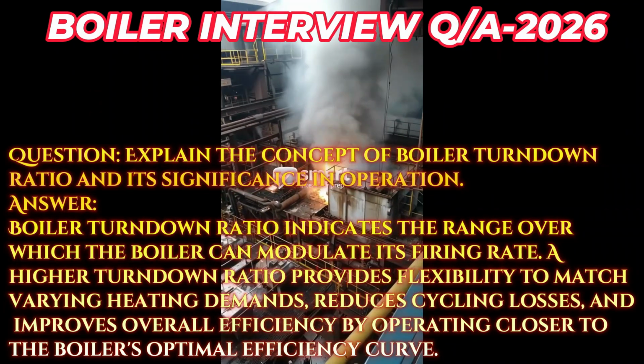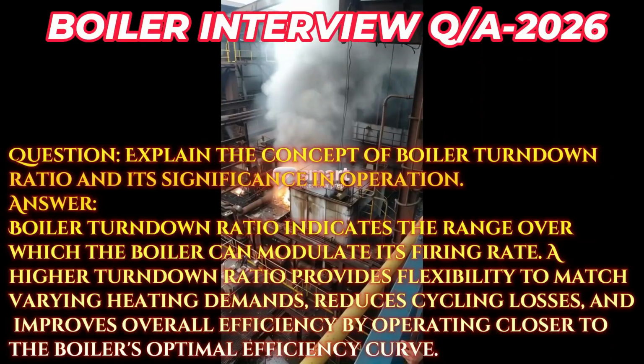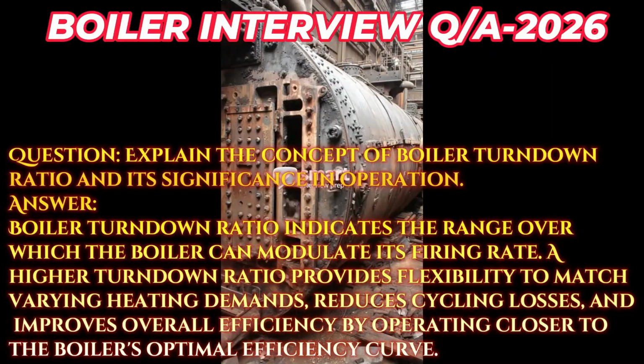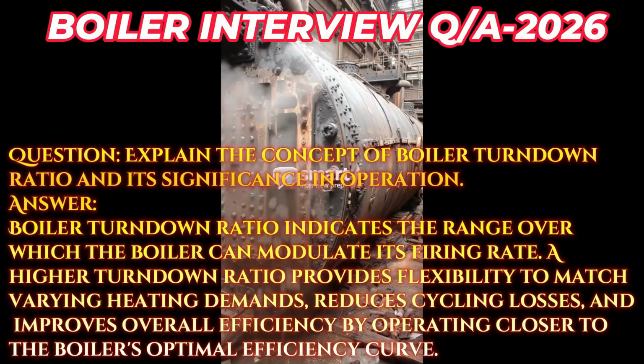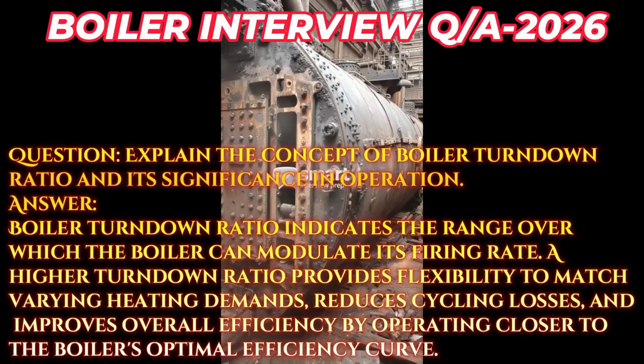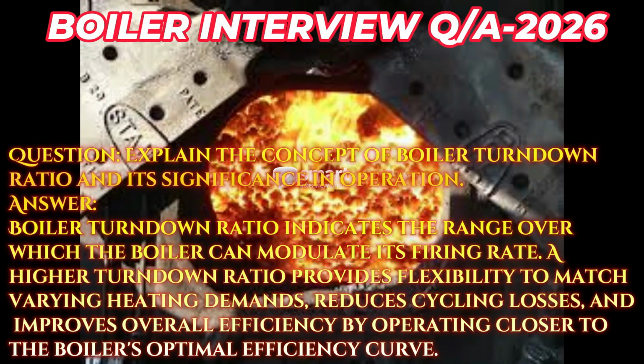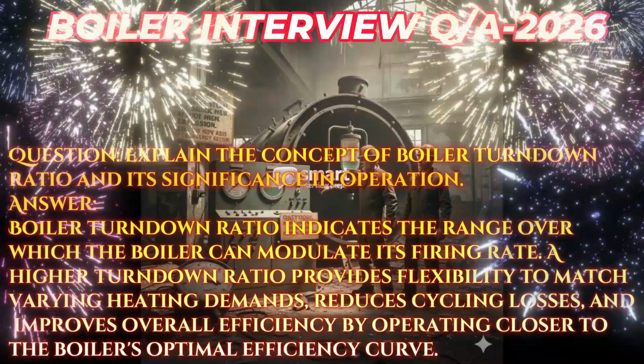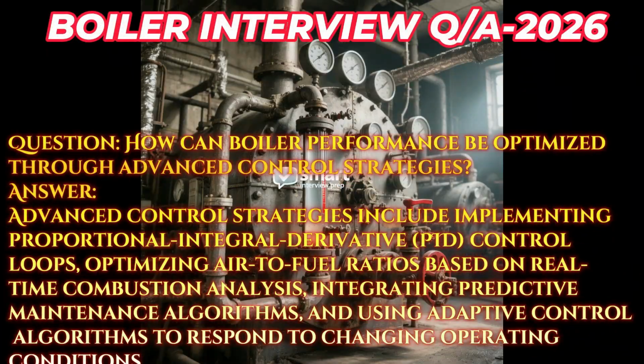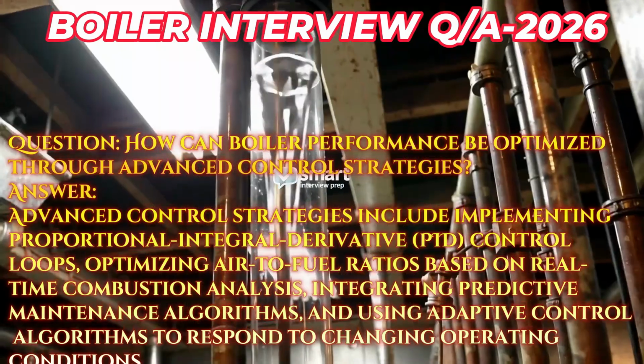Answer: boiler turndown ratio indicates the range over which the boiler can modulate its firing rate. A higher turndown ratio provides flexibility to match varying heating demands, reduces cycling losses, and improves overall efficiency by operating closer to the boiler's optimal efficiency curve. Question: how can boiler performance be optimized through advanced control strategies?